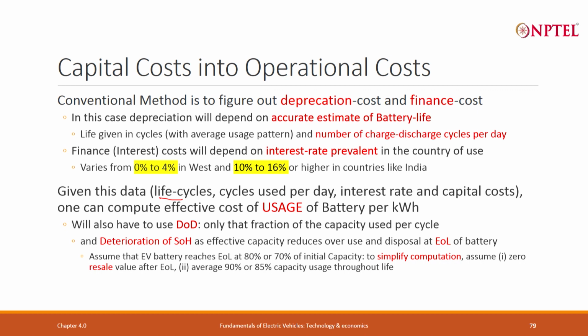So do you understand what I am saying? Suppose when the battery is new, we are using 0.85. When the battery is nearly end of life, I am using 0.85 into 0.8. So what will the average cycle consume? Average cycle will consume 0.85 into 0.9, the average between 1 and 0.8. That will simplify the calculation. If you want a more detailed calculation, you can do it, but it gets more complicated.